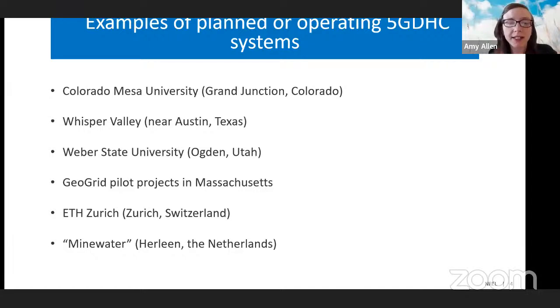The so-called mine water system in the Netherlands leverages water that has flooded abandoned mines as a source for heating and heat rejection, and has evolved over time from a so-called fourth generation system operating at higher temperatures in heating and lower temperatures in cooling to an ambient loop operating at close to air temperature. And the various forms of these systems illustrate how building loads can synergistically offset each other and leverage ground heat exchangers and also surface water heat exchangers, as well as systems like mine water in the Netherlands to provide conditioning for the overall loop.